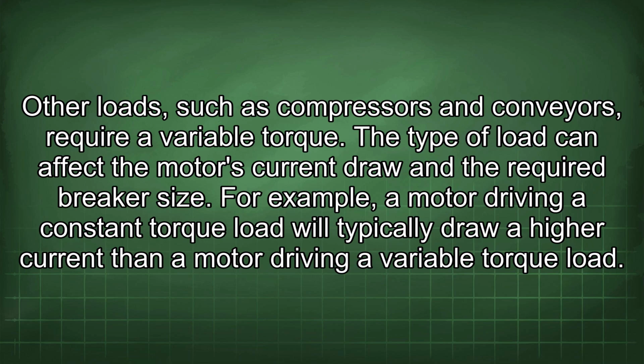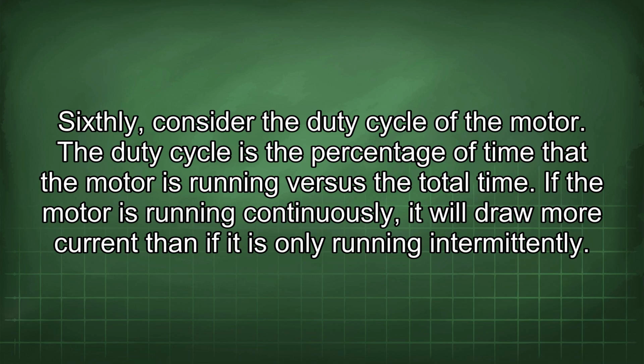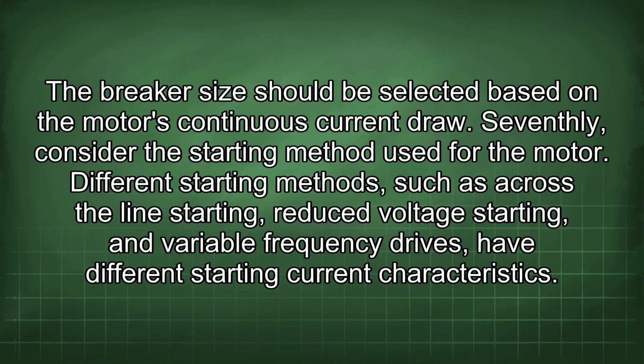Sixthly, consider the duty cycle of the motor. The duty cycle is the percentage of time that the motor is running versus the total time. If the motor is running continuously, it will draw more current than if it is only running intermittently. The breaker size should be selected based on the motor's continuous current draw.